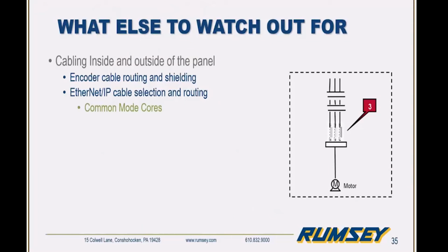Okay, other things to keep an eye out for: if we're using an encoder, we want to make sure we're using the properly rated encoder cable and shielding, and that it's routed in the correct manner to prevent presenting any issues for us. Another noise-related thing would be using the properly rated communication cables and routing those accordingly as well. I know Rumsey has the properly rated comm cables available when you're doing an installation, to make sure you're not bringing any noise into your system.